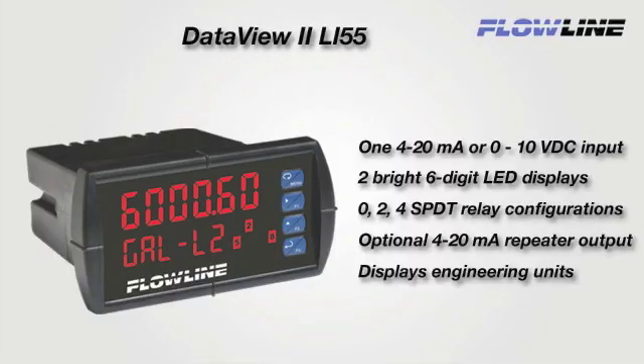And today, I would like to talk with you about Flowline's new DataView 2 LI55 Universal Display and Controller. So let's get started. The general purpose meter displays engineering units with a 4 to 20 milliamp or 0 to 10 VDC transmitter input channel and is offered in three configurations with optional 2 or 4 relays, 4 or 8 set points, and an isolated 4 to 20 milliamp repeater.